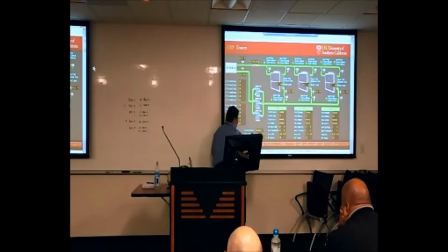We have the flow rate going up to the towers. It's on the header that goes up to the top of the towers. It's on a vertical line. That's the flow meter. That's the current flow rate. And then we have a chemical alarm indication right here if there's a problem with the chem feed panel. We have an outside air temperature wet bulb right now reading 63 degrees Fahrenheit. We have a makeup water meter right here, roughly reading about 2 million gallons since we got the thing up and running last fall. So that's the total accumulated makeup so far since, let's say, sometime in November.